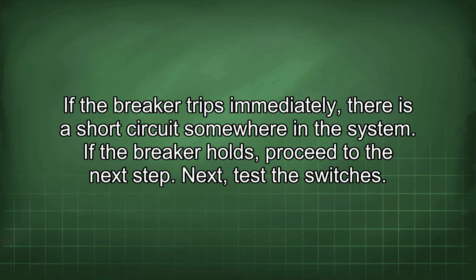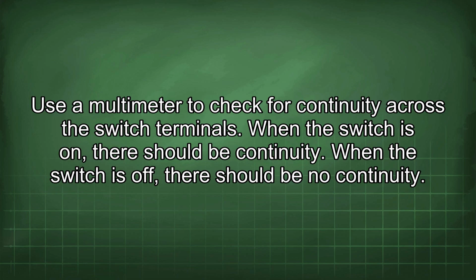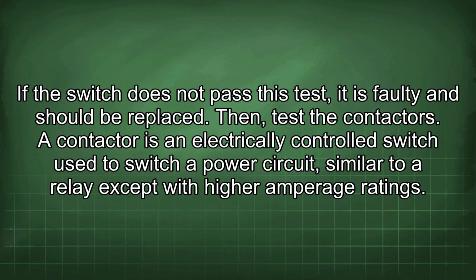Next, test the switches. Use a multimeter to check for continuity across the switch terminals. When the switch is on, there should be continuity. When the switch is off, there should be no continuity. If the switch does not pass this test, it is faulty and should be replaced.